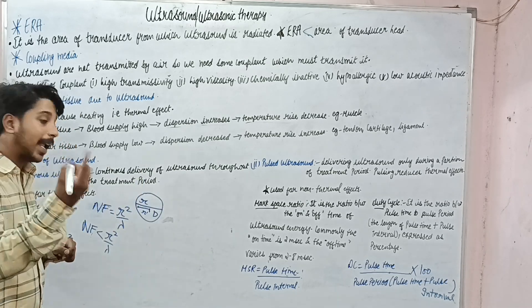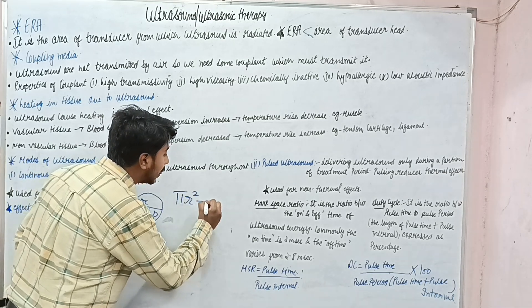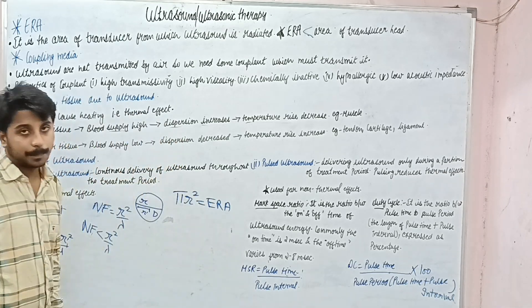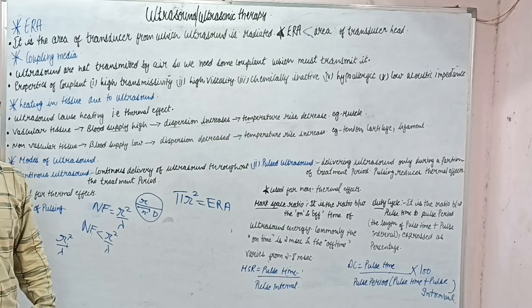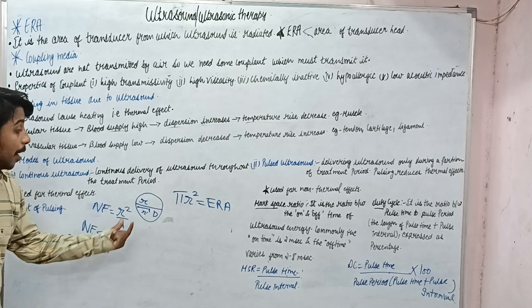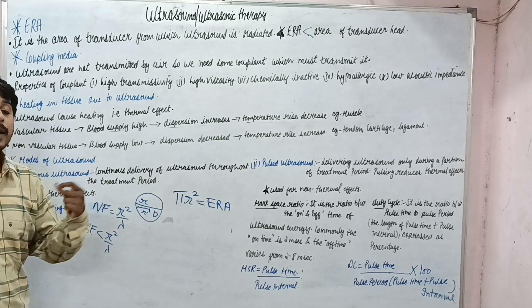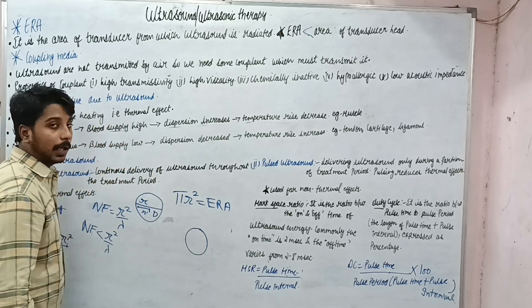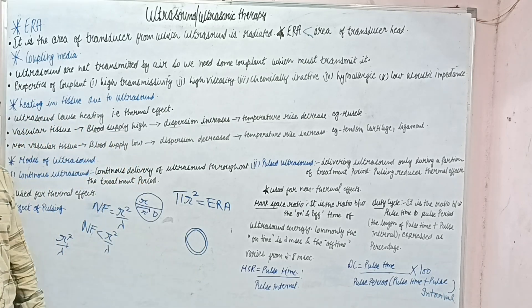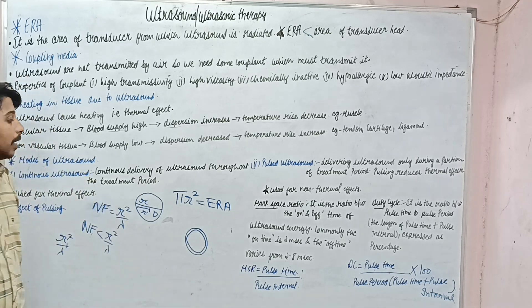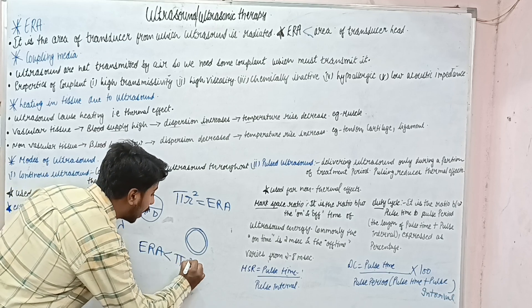To calculate the effective radiation area, you use the actual radius: pi R squared equals the effective radiation area. But your answer must be less than the actual area, because radiation is not occurring from the whole radius. The inner circle of the transducer head is the only part from where the ultrasound wave is coming, so ERA will be less than pi R squared.